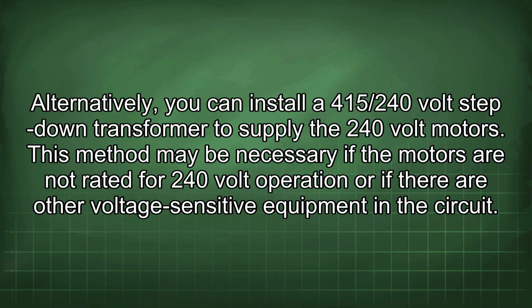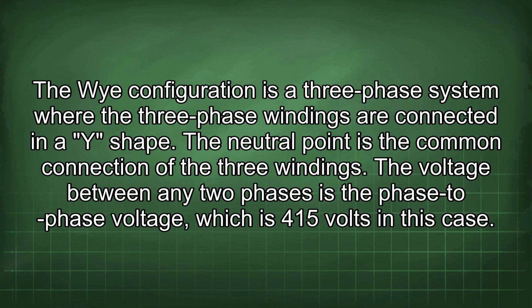Alternatively, you can install a 415/240-volt step-down transformer to supply the 240-volt motors. This method may be necessary if the motors are not rated for 240-volt operation or if there are other voltage-sensitive equipment in the circuit. The Y configuration is a three-phase system where the three-phase windings are connected in a Y shape. The neutral point is the common connection of the three windings.